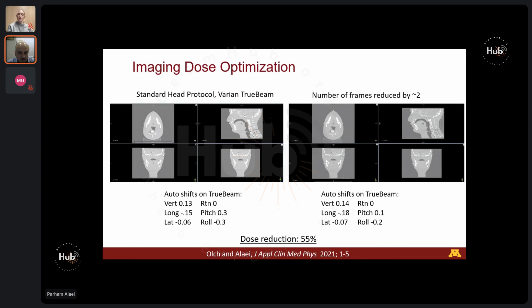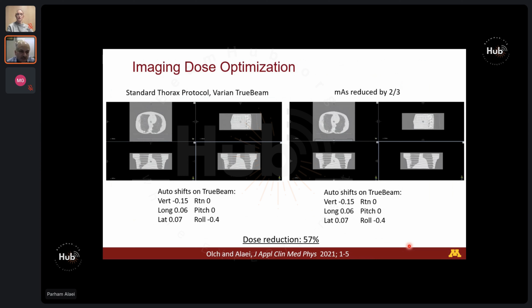And by the same token, using the thorax portion of the phantom, doing the same study, the milliamp second or current time product was reduced by 2/3. The dose was reduced by 57%, and the auto shifts worked, so it was fine. Again, bony anatomy matching. So bony anatomy matching is fairly easy to implement. If you want to look at soft tissue contrast, it becomes trickier to figure out what to do and how much we can reduce the dose.